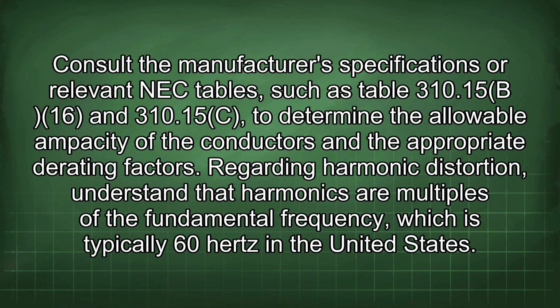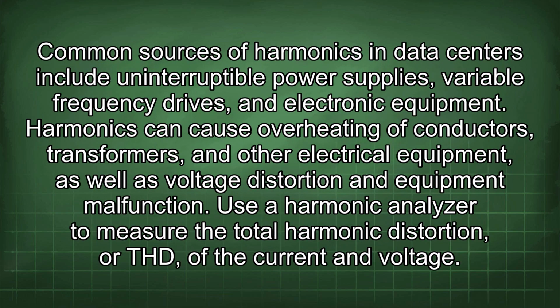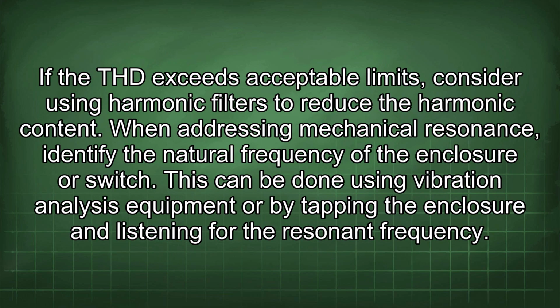Regarding harmonic distortion, understand that harmonics are multiples of the fundamental frequency, which is typically 60 Hz in the United States. Common sources of harmonics in data centers include uninterruptible power supplies, variable frequency drives, and electronic equipment. Harmonics can cause overheating of conductors, transformers, and other electrical equipment, as well as voltage distortion and equipment malfunction. Use a harmonic analyzer to measure the total harmonic distortion, or THD, of the current and voltage. If the THD exceeds acceptable limits, consider using harmonic filters to reduce the harmonic content.